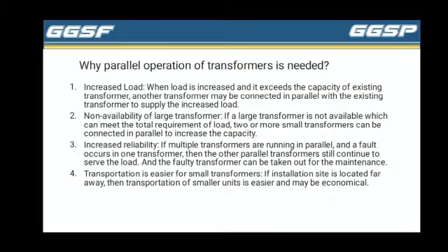Third, increased reliability. If multiple transformers are running in parallel and a fault occurs in one transformer, then the other parallel transformers still continue to serve the load, and the faulty transformer can be taken out for maintenance. Fourth, transportation is easier for small transformers. If the installation site is located far away, then transportation of smaller units is easier and may be economical.